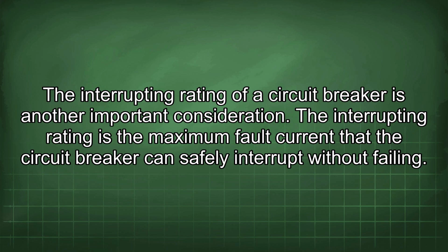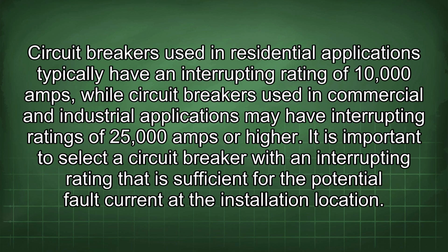The interrupting rating of a circuit breaker is another important consideration. The interrupting rating is the maximum fault current that the circuit breaker can safely interrupt without failing. Circuit breakers used in residential applications typically have an interrupting rating of 10,000 amps, while circuit breakers used in commercial and industrial applications may have interrupting ratings of 25,000 amps or higher.